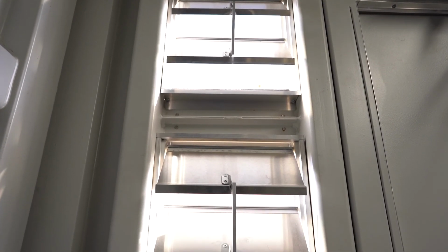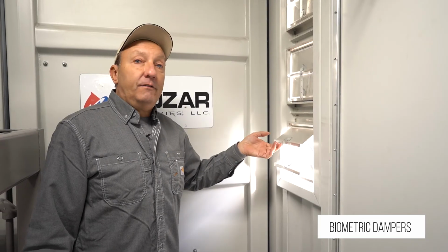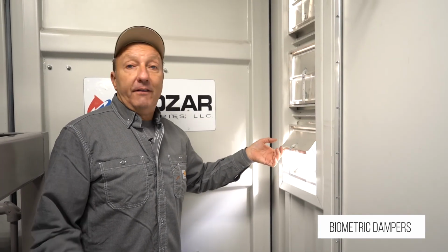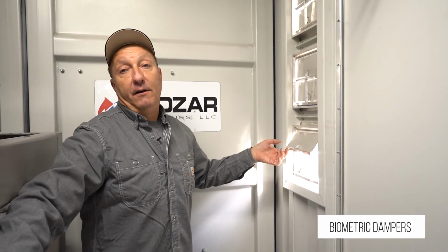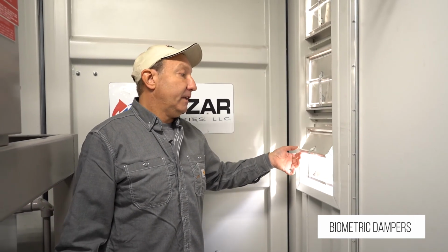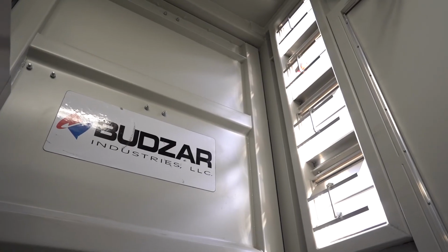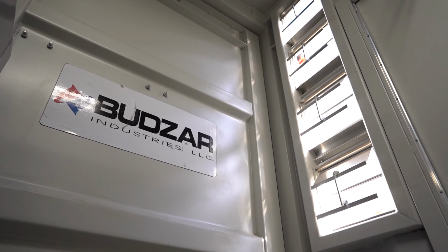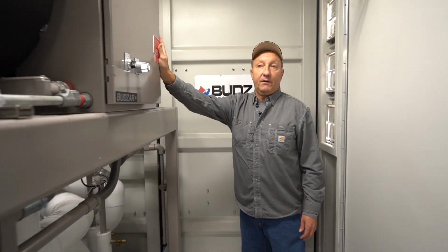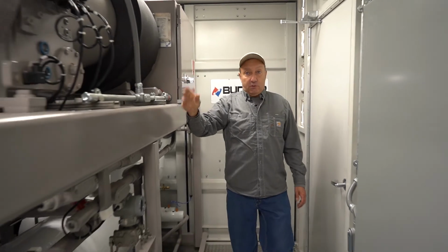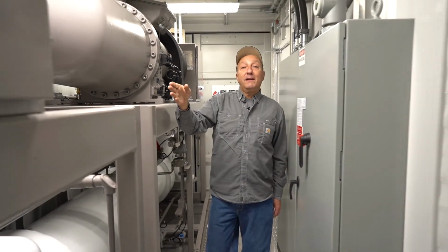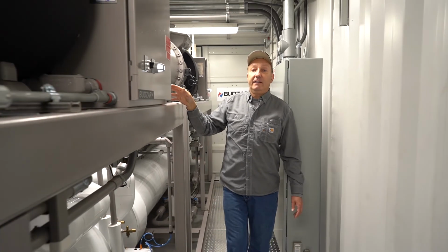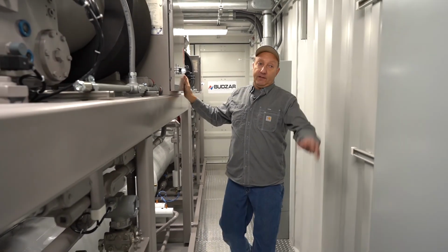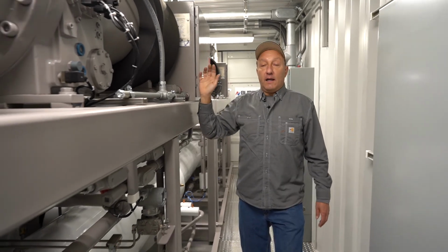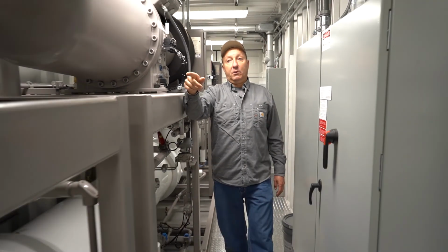Okay, here we are at the back end of our container system, and these are the barometric dampers. When the fan is running, these open basically to the level of airflow being moved through the container. When one fan is on, it opens slightly. When both fans are on, it opens more, allowing more circulation and airflow through the container. This is circuit 3, the farthest one. We're moving back towards circuit 2. Again, they're completely identical circuits, except circuit 1 has the LEL propane leak detection system. Each has a main cabinet, control cabinet, and we go all the way back to circuit or chiller 1.